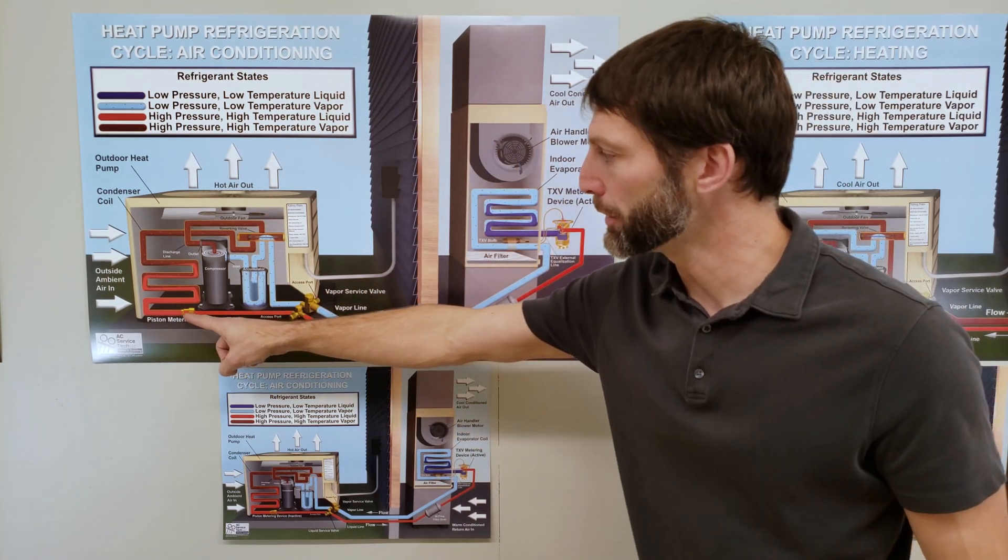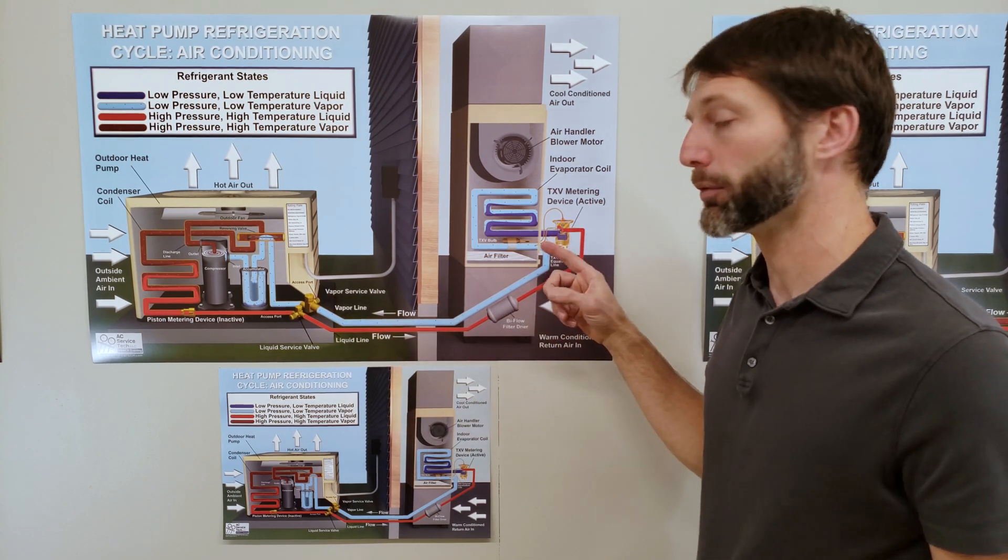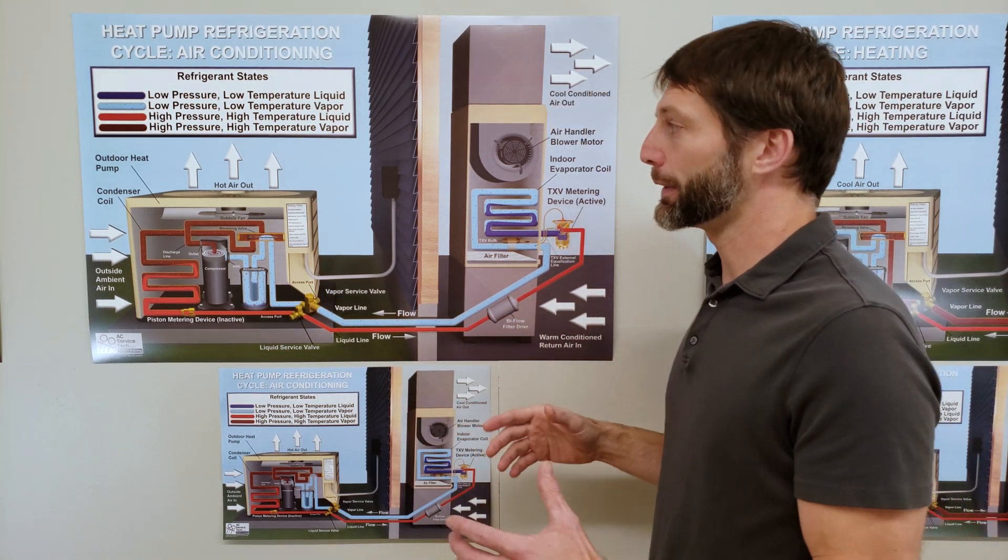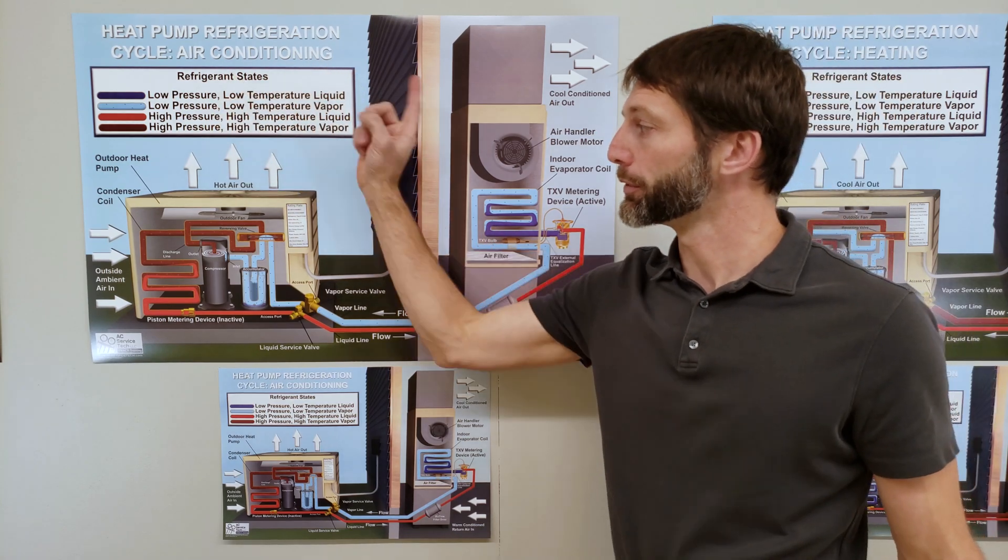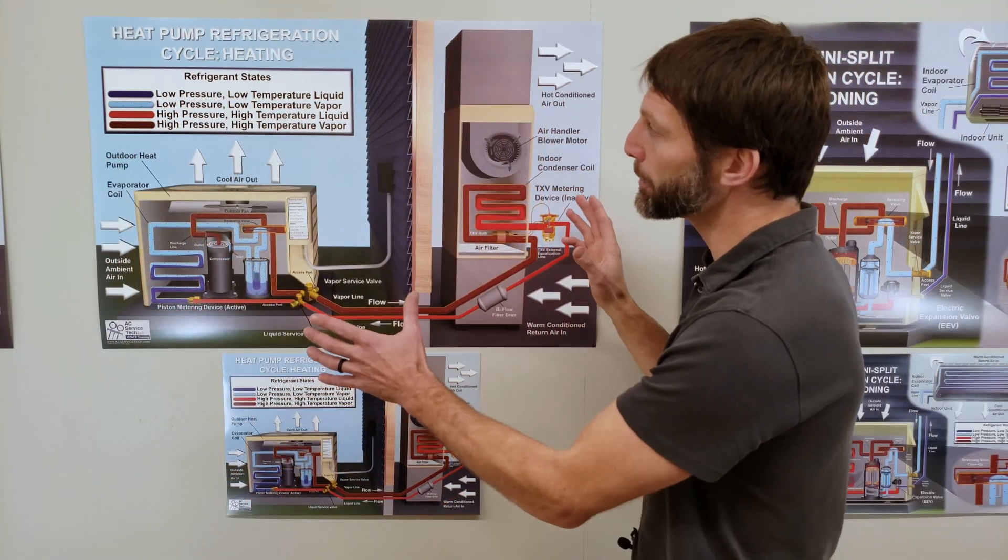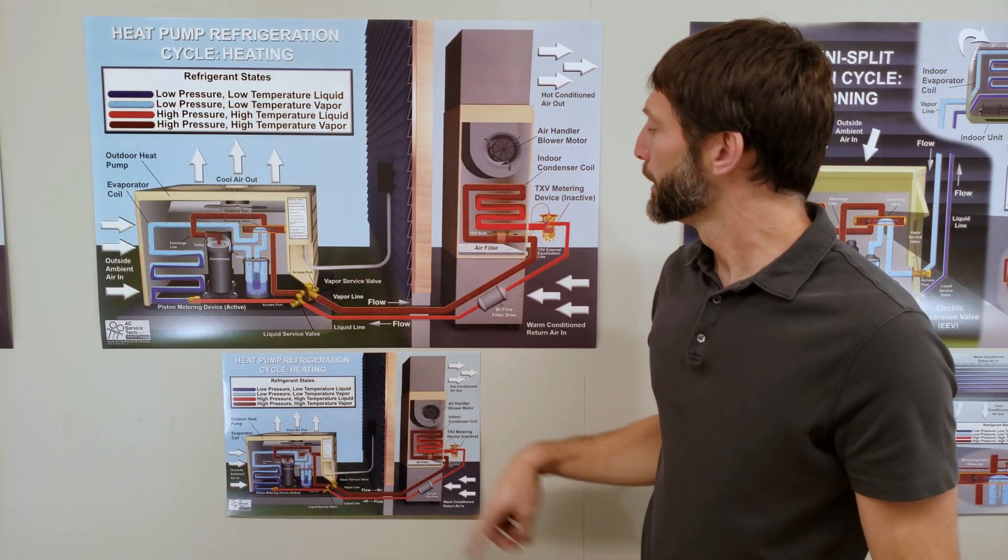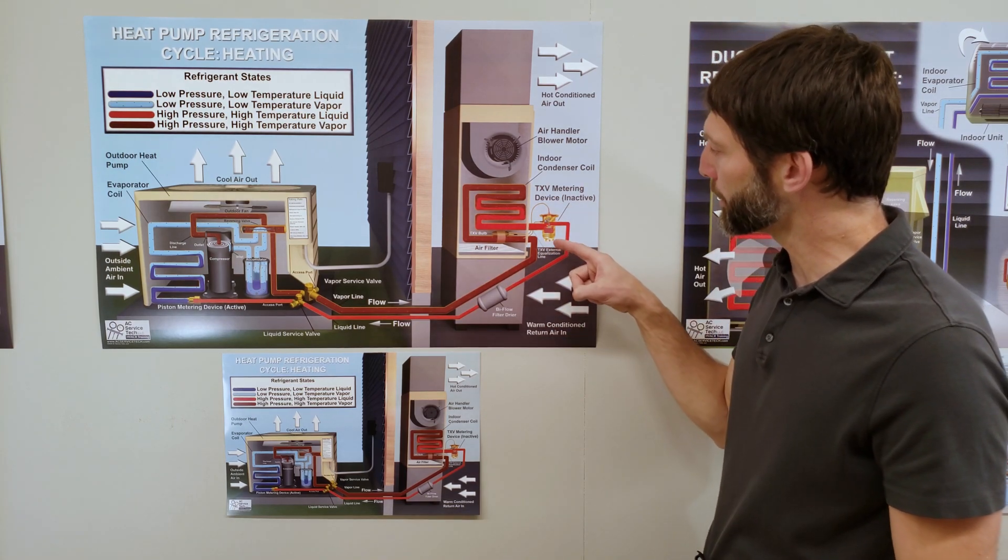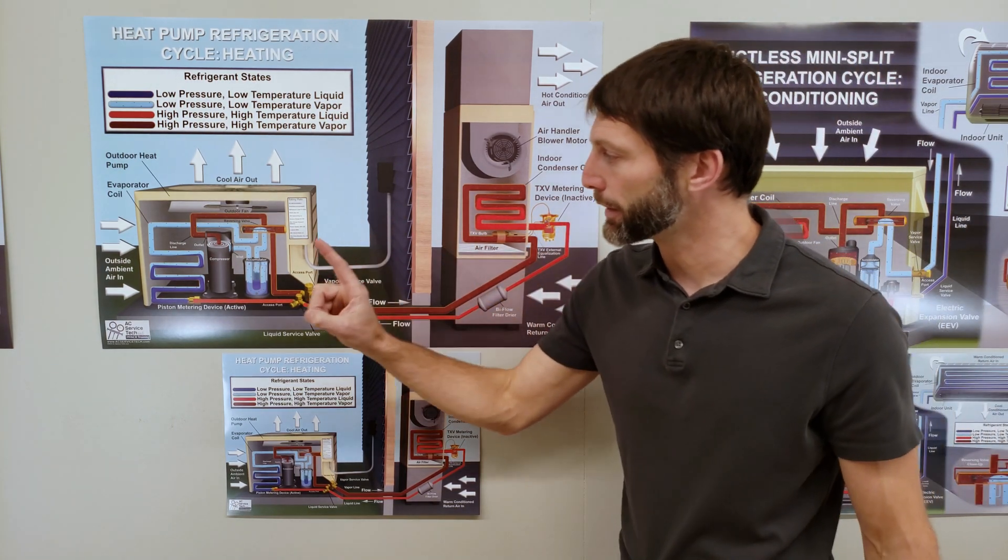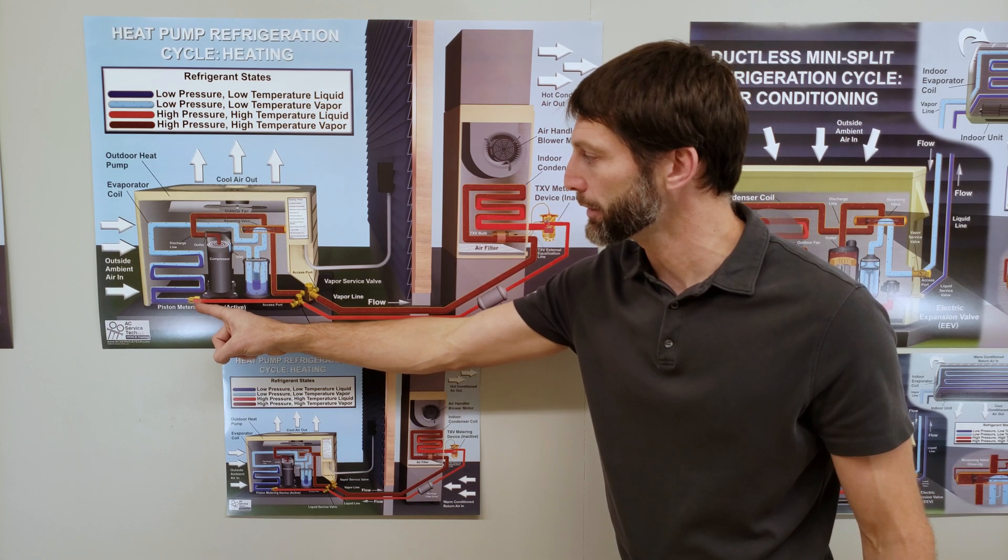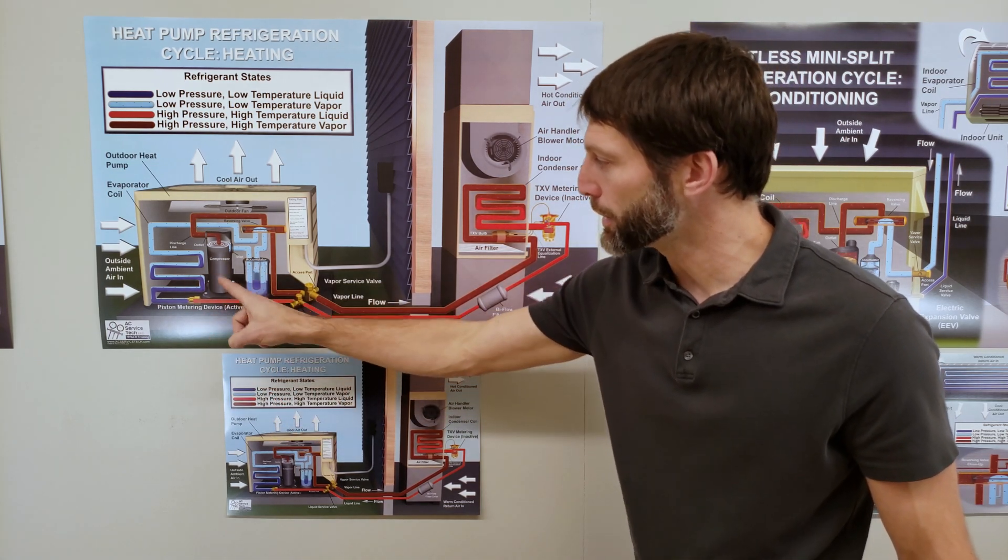You have two metering devices, one here and one here. One's active and one's inactive, and that changes depending on what mode you're in. This one's in heating mode and it's indicated right there. You have an inactive metering device here which is your thermostatic expansion valve, and here's your active metering device out here. You do see a change in pressure.